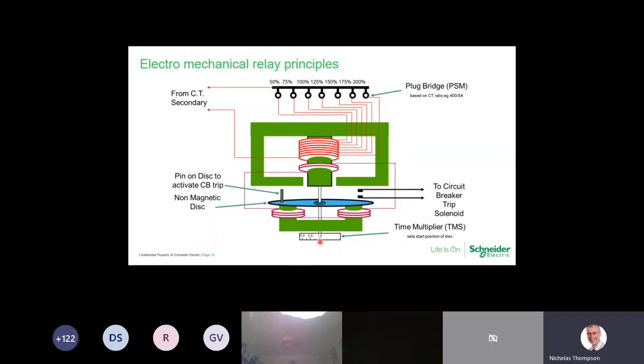In this example here, it's 1, so it's at the furthest point, and when we move it to 0.6, the peg is moving to somewhere in this point here. So it's a lot closer to the trip contacts than it was if it was at 1. Ultimately, it's going to take a shorter time to actually get to the shorting contacts.